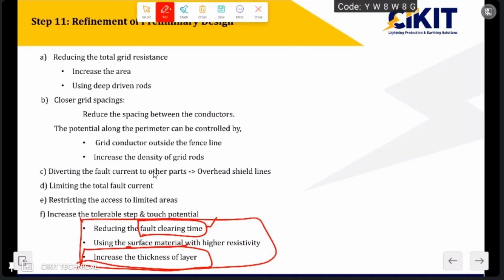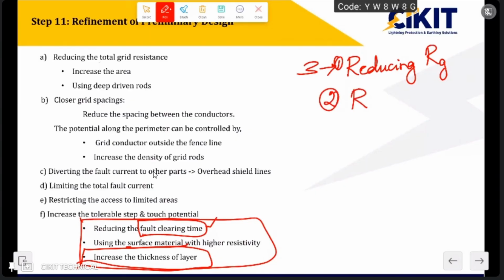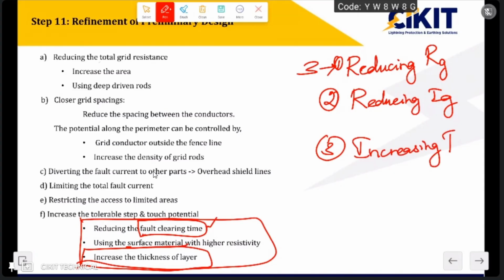So if I take this modification, the standard has mentioned 3 points. The first one is related to reducing Rg, which is nothing but the grid resistance value. The second one is reducing the value of Ig. And the third one is increasing the value of the tolerable limit. So by using these three methodologies, we can ensure that the design which we are providing is safe.